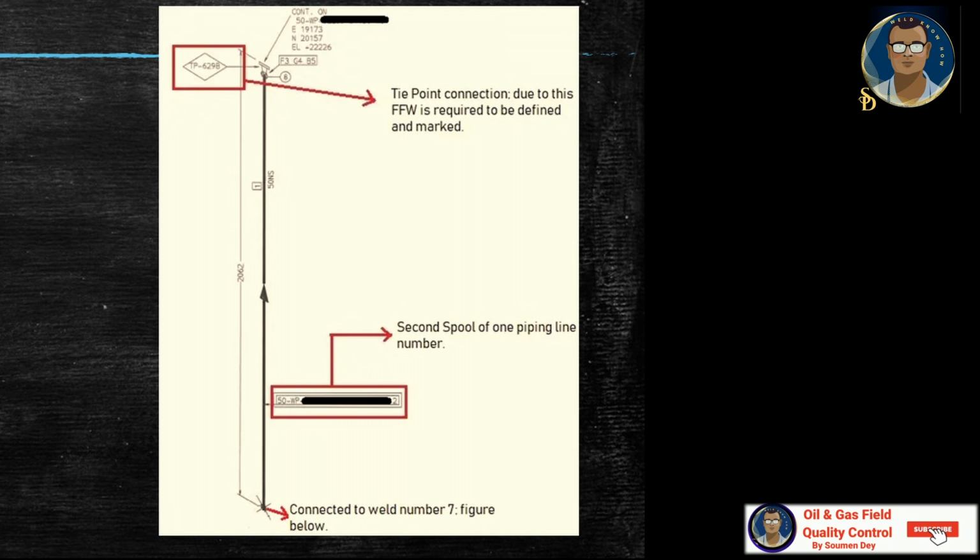Isometric drawing defines shop or field fabrication also. Isometric drawings also inform which piping should be constructed at the fabrication shop and which should be assembled at the construction or platform field itself. The complete piping system is separated into pieces that are transported to the site for erection. These small pipe pieces are termed piping spools. One sheet of isometric drawing normally has a few spools.